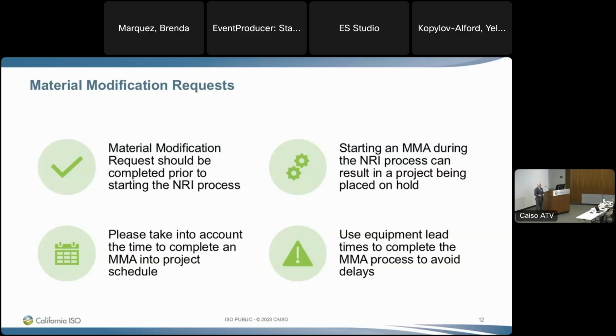The material modification request should be completed prior to starting the NRI process. That doesn't mean you start the MMA process or start the NRI process—it means you complete the MMA process before you start the NRI process. The MMA is a modification to the LGIA, and as I mentioned before, the LGIA is the foundational document that says you can interconnect to the grid. So if you're modifying that with equipment not approved at this time and try to start the NRI process, you're trying to start it with equipment that's not approved.